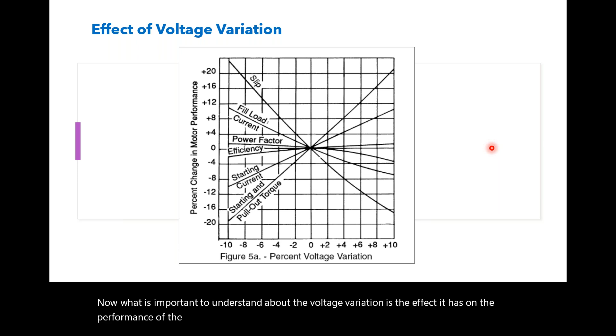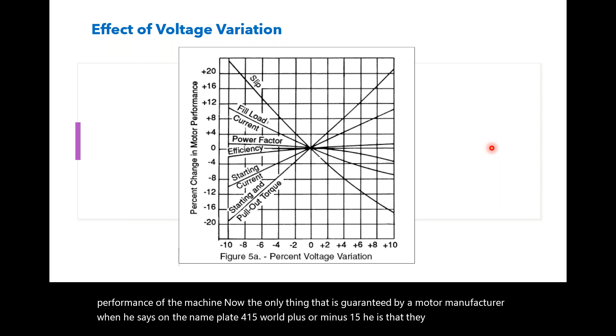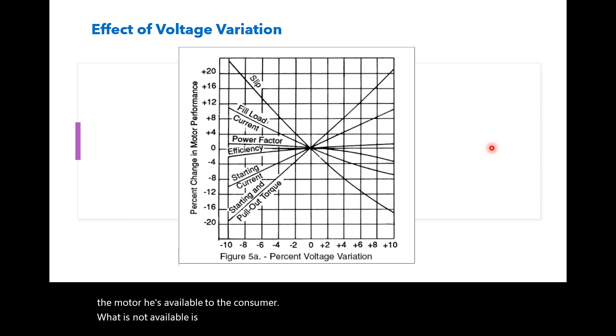Thank you. Now, what is important to understand about the voltage variation is the effect it has on the performance of the machine. The only thing guaranteed by a motor manufacturer when he says on the nameplate 415 volt plus or minus 10% is that the rated output of the motor is available to the consumer. What is not available is control on the parameters. Just take a look here. The 0 here denotes the rated voltage 415. You have minus 10 here and plus 10 here.